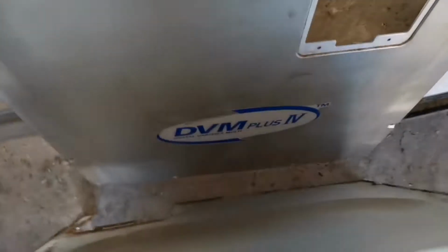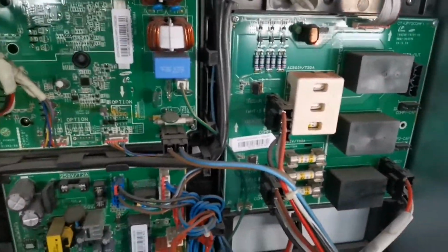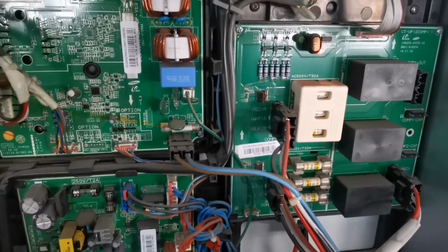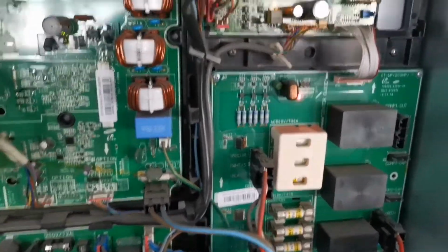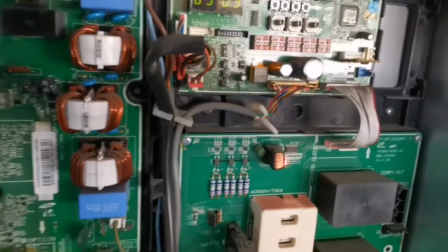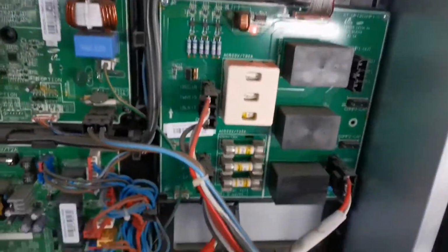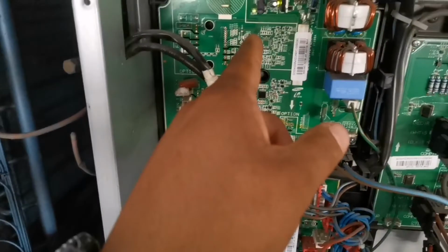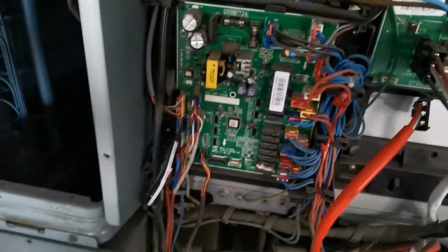Now this system being the DVM+4 is the earlier model, and the ones that I've got most of my videos on are the DVM-S. The difference between the two is the DVM-S is an all inverter system. So the compressors are inverters, the condenser fan motor is an ECM, and right here you can see this is the inverter circuit for the fan motor.